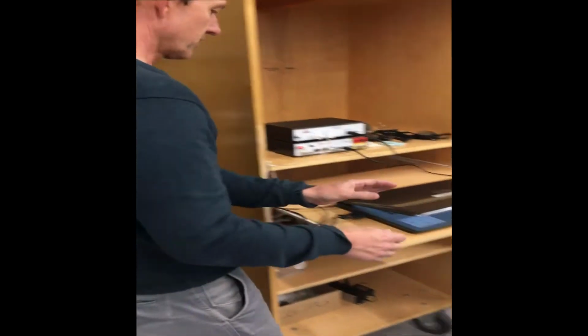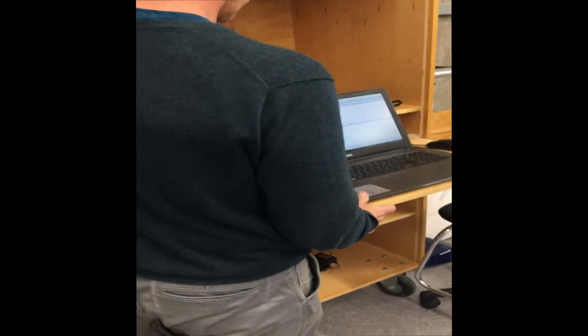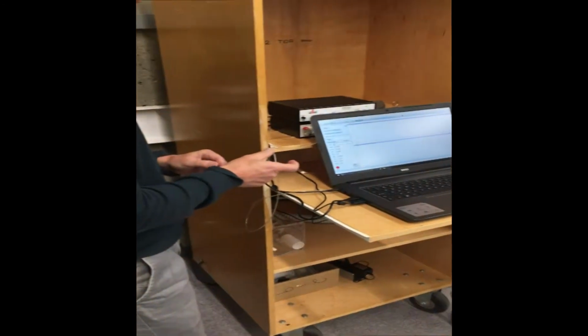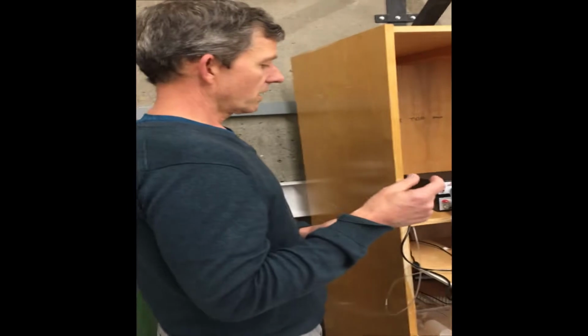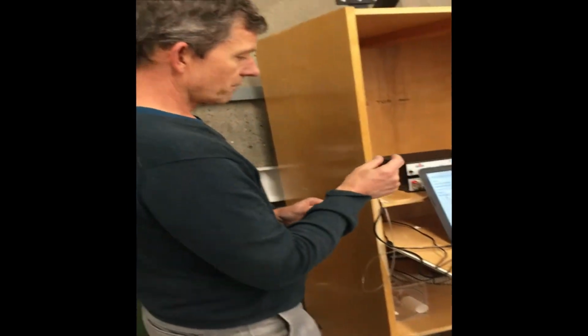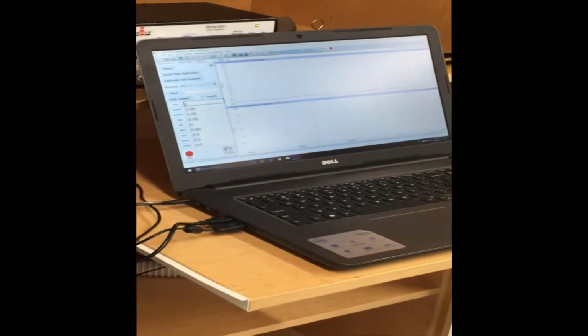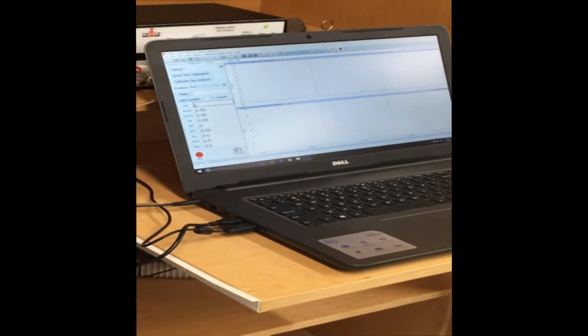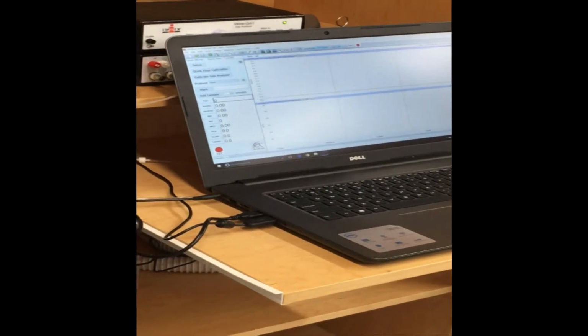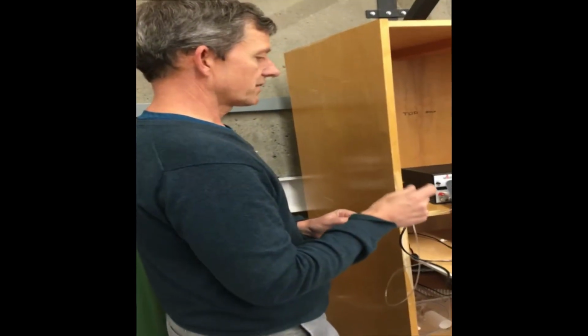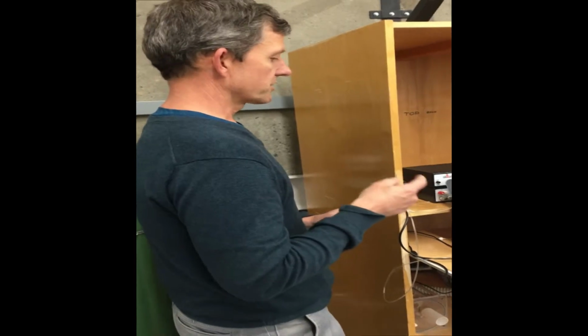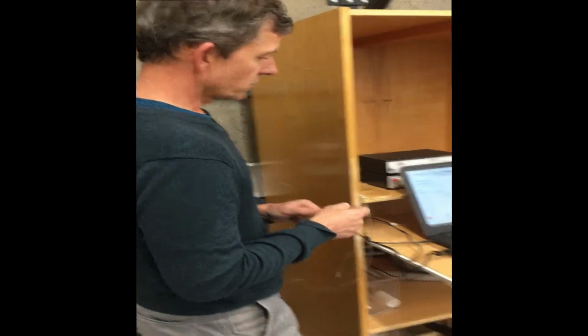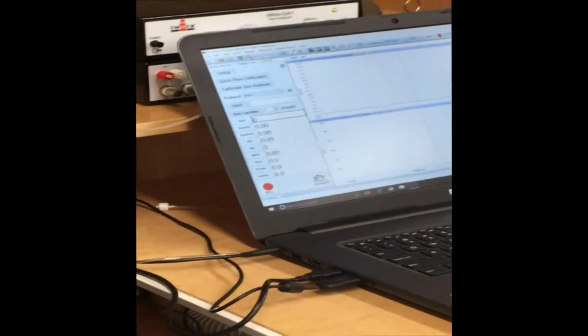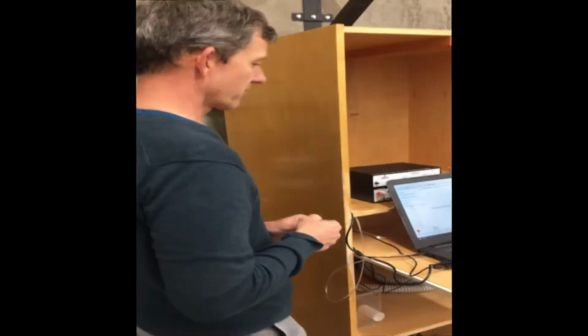To calibrate this is relatively straightforward. What I've opened up here is a file that will allow us to monitor the gas. I've opened up a setting that we're actually going to use for the VO2 max test, but this file will allow us to look at CO2 continuously and at oxygen continuously, and based on that we're able to determine what our oxygen and CO2 concentration is. On the screen here in real time you'll see what the oxygen and the CO2 concentration is. Then we can go back with our single cursor and measure what that value actually is.